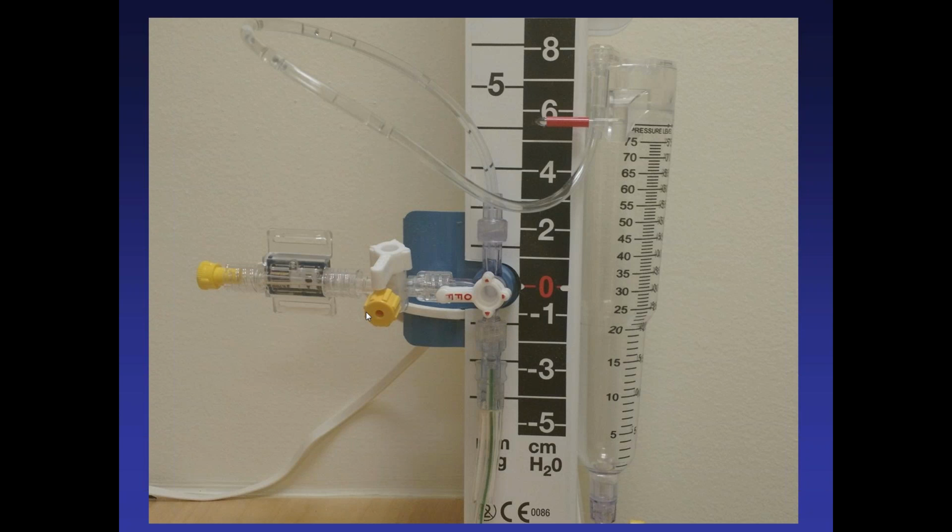Another pearl, I guess, I don't know if it was a Montefiore specific pearl, is if you get called to see the patient for high ICP, or just for any reason you're in there and you see this yellow cap on here, consider re-zeroing it yourself. Because the nurses for A lines and central lines are used to having the white cap on here. The white cap has a hole in the middle of it, so it's always open to atmosphere. So what the nurses will sometimes do is turn the stopcock this way to have the transducer open to atmosphere, and they're used to having the white one with the hole, but the yellow one doesn't have a hole. So they'll zero it with this closed, which is not appropriate, and then you'll get these wacky numbers.